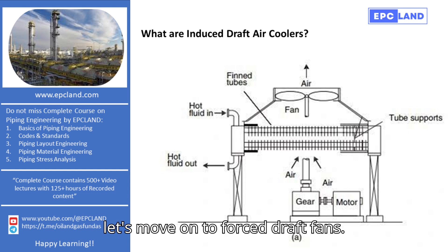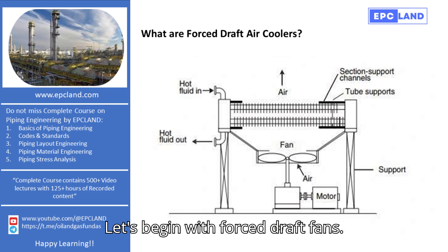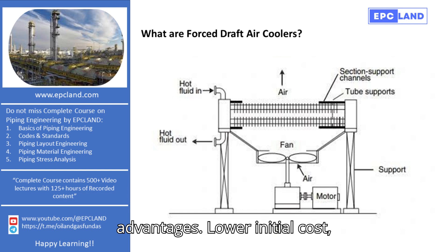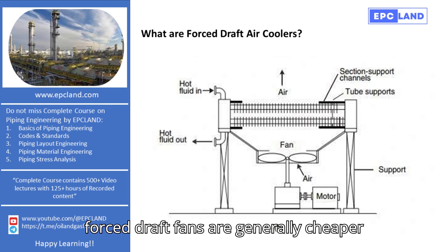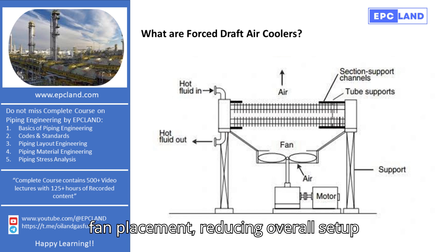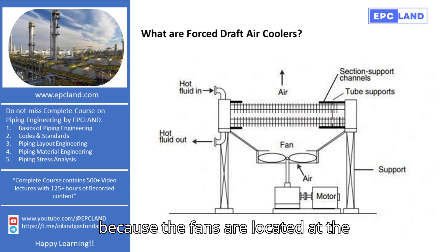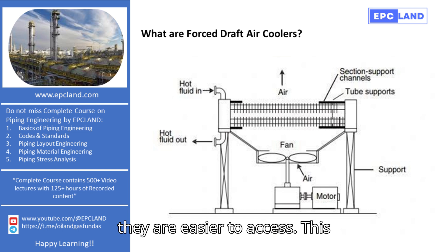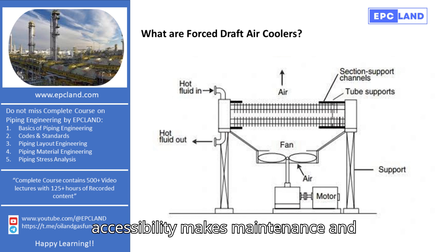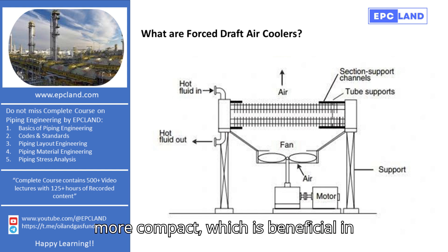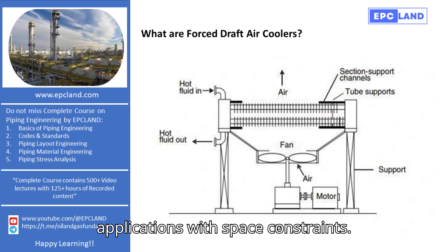Now let's move on to forced draft fans. These fans are known for several advantages. Lower initial cost — forced draft fans are generally cheaper to install. They push air into the system, which can simplify ducting and fan placement, reducing overall setup costs. Easy maintenance — because the fans are located at the intake or lower levels of the system, they are easier to access, making maintenance and repairs simpler and more straightforward. Compact design — forced draft fans can be more compact, which is beneficial in applications with space constraints.